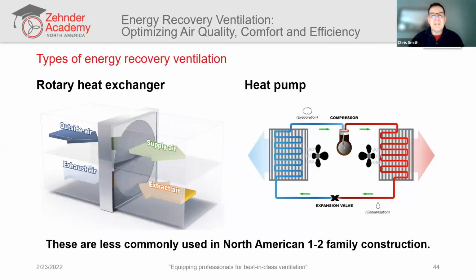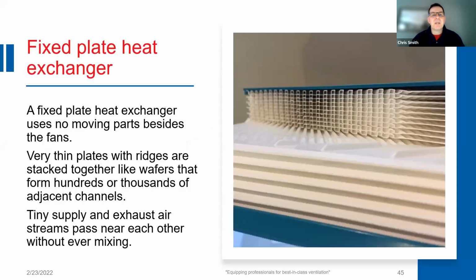Just to mention again, in both of these, you have a supply fan and exhaust fan and some way of moving or transferring the heat between the two airstreams. A fixed plate heat exchanger is the much more common type of device that's used in North American 1 and 2 family energy recovery solutions. So we're going to focus on fixed plate heat exchangers for the rest of the presentation. A fixed plate heat exchanger uses no moving parts besides the fans. So you have a supply fan and exhaust fan as you do with the others, but other than that, you just have this system of fixed plates.